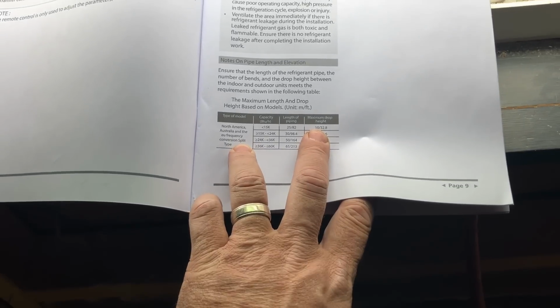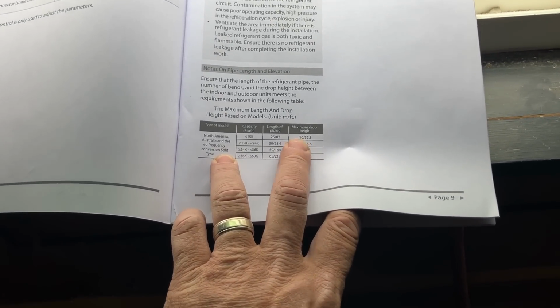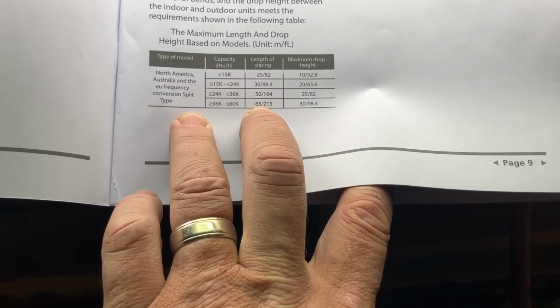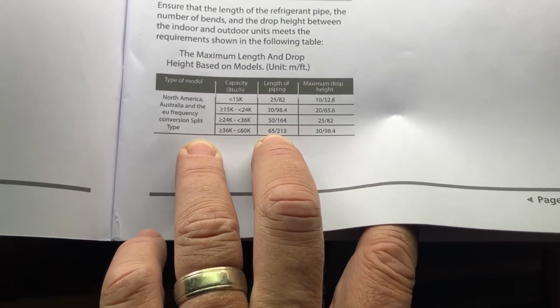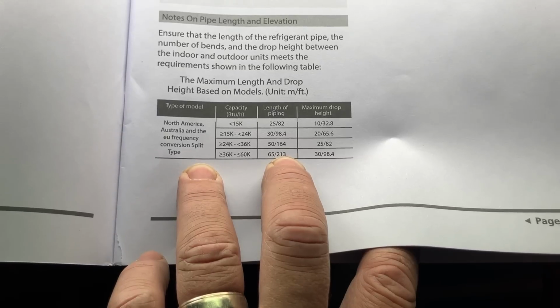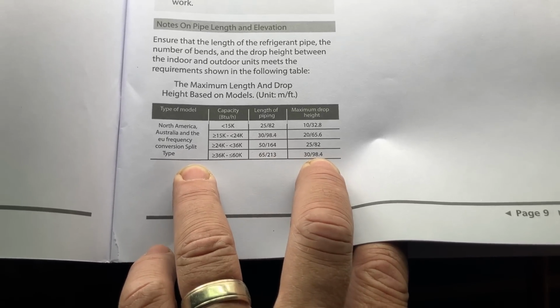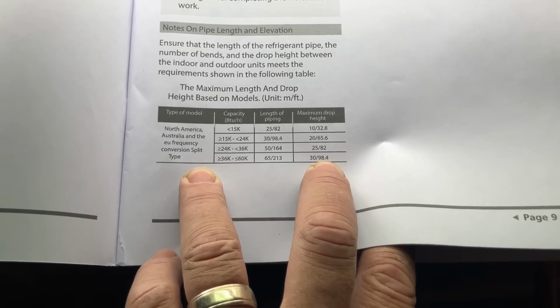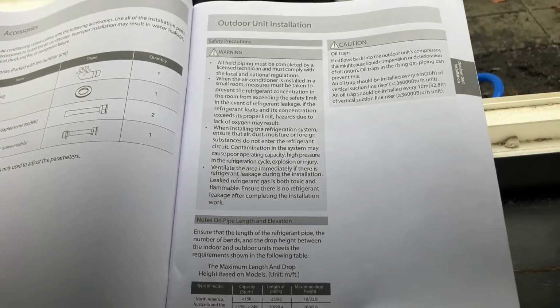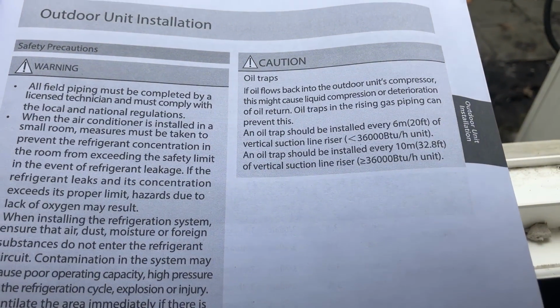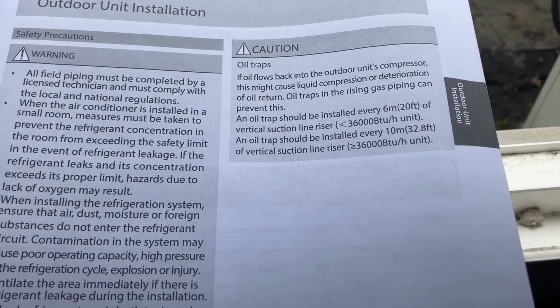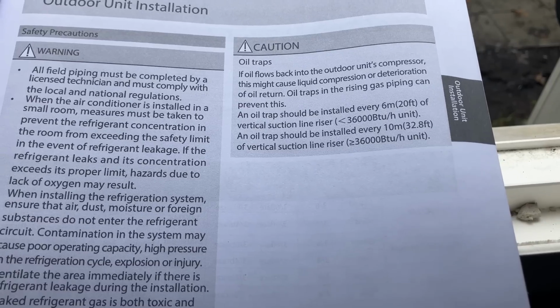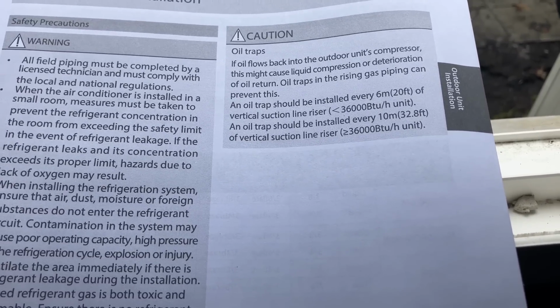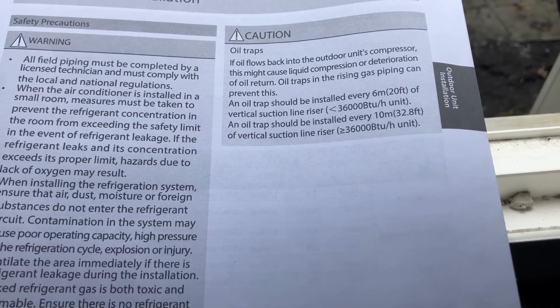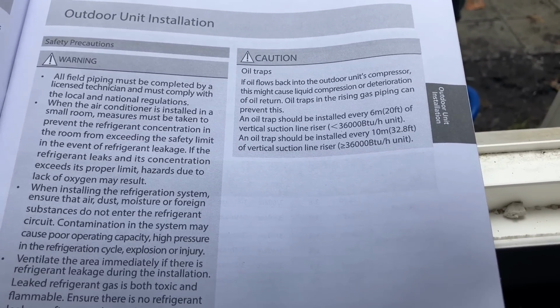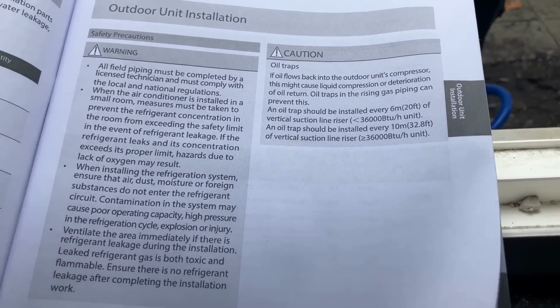We're reading the manual, looking at some line set specifications, minimum and maximum. We're at 60,000 BTUs, so we're going to have a maximum length of 213 feet and a maximum drop of almost 98.4 feet. We're going through the manual. We're also talking about oil traps. Keep this in mind: an oil trap must be installed for every 20 feet of vertical suction line riser, and also every 32.8 feet of vertical suction line riser. So keep that in mind, oil traps, if you're going to be over 20 and 30, almost 33 feet.